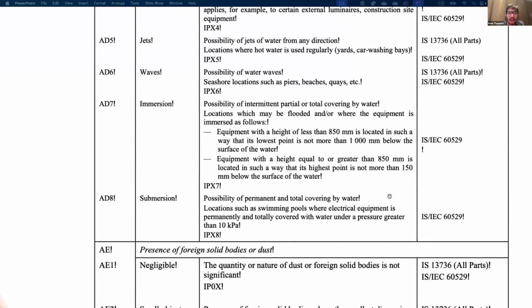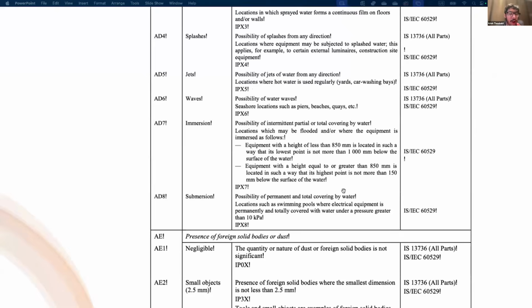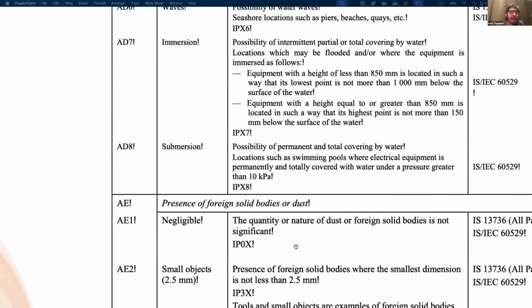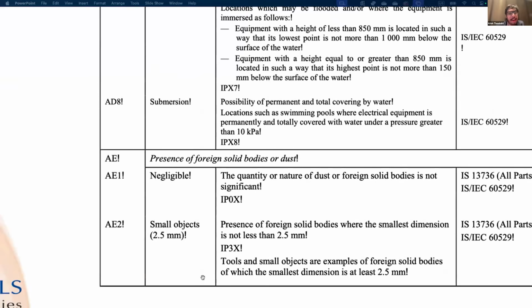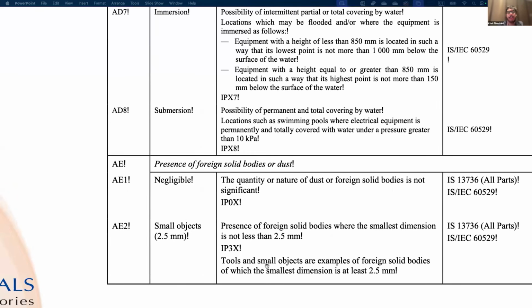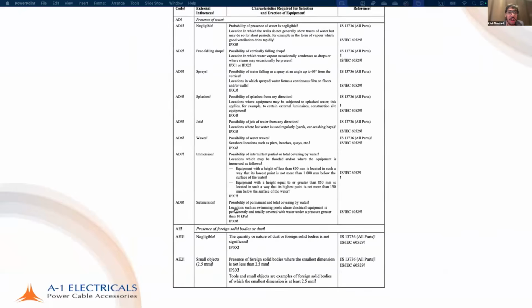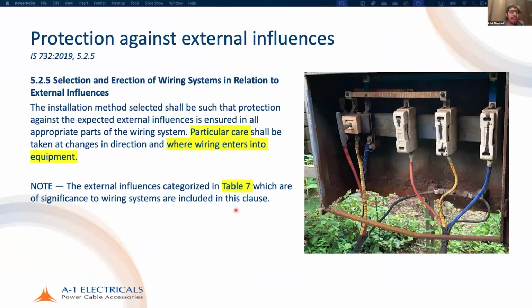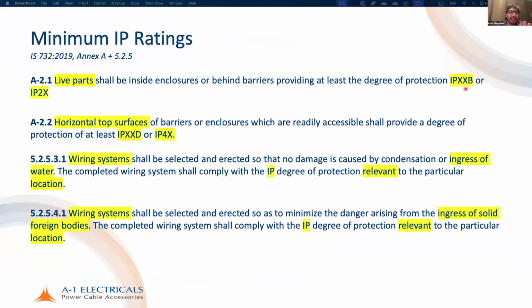Yeah. Now, as somebody mentioned in the chat, all the provisions are as per IS 732. Presence of dust is also there: negligible dust, small objects. You have to read the standard and figure out what is your relevant level of external influences, and accordingly you have to select the level of ingress protection required. But no matter what, the basic requirements are always IPXXB or IP2X, and horizontal surfaces IPXXD or IP4X. Anything beyond this according to the external influences, which in most cases will be there.